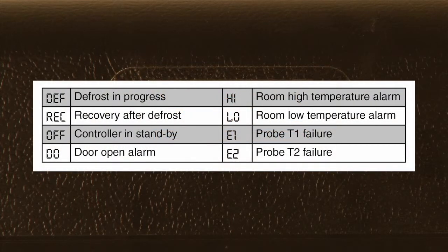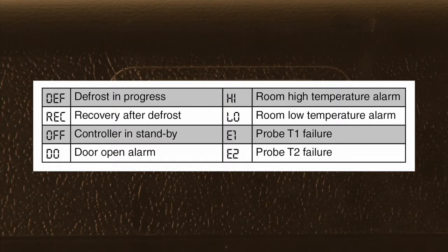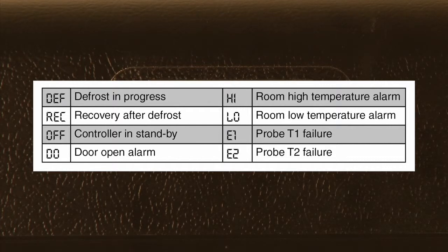DEF would indicate that there's a defrost in progress. REC indicates that we're in recovery mode, out of defrost and returning the coil to operating temperature. This indicates that we would be in fan delay — the evaporator fans would be off until we reach the end of the recovery mode and fan operation returns.